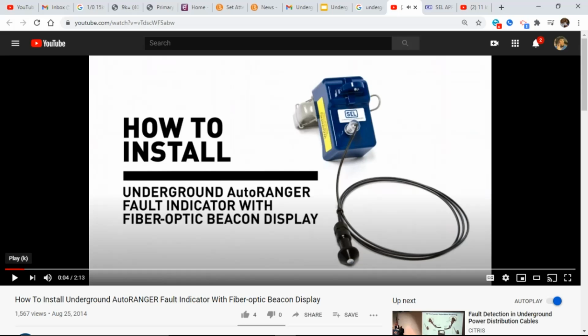Now, just a quickie here, because this is a little bit different. The assembly, that blue assembly that you see right there, is pretty much the same assembly, but these are more modern, a little bit more pricey. They actually have a fiber optic cable that goes into the indicator, and this mounts on the outside of the transformer. If you have a fault on the conductor, this will flash a red light. Now these are great. We've used them before. These are fantastic to use at night, because you're just driving down the road looking at flashing lights. You're going to have a red flashing light, and in the next span it's not going to be flashing. That's going to tell you which span it's in. But that's the difference in this fault indicator.